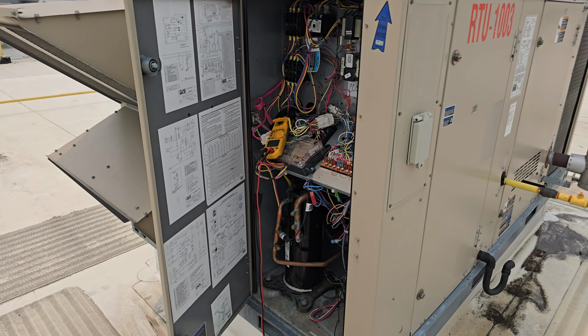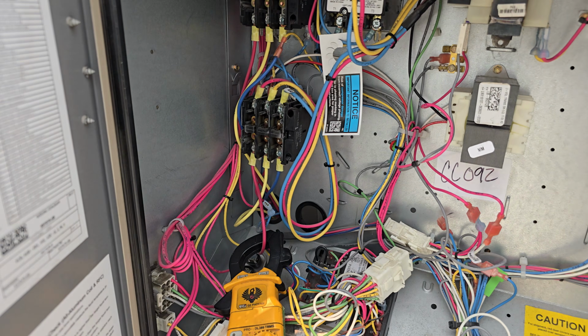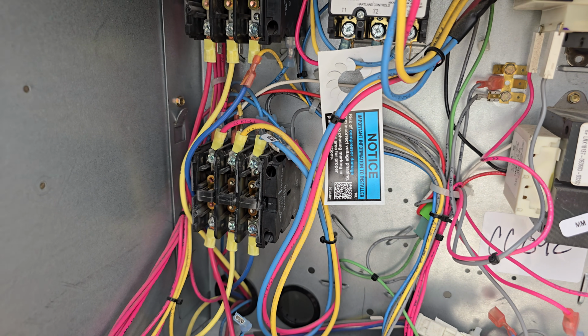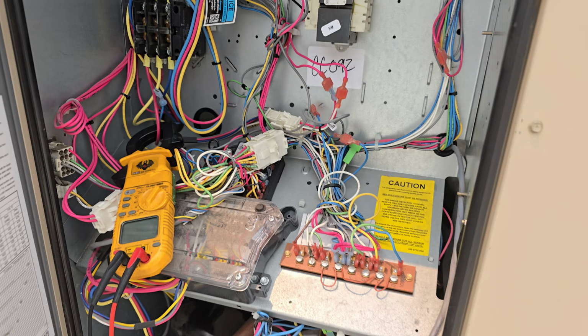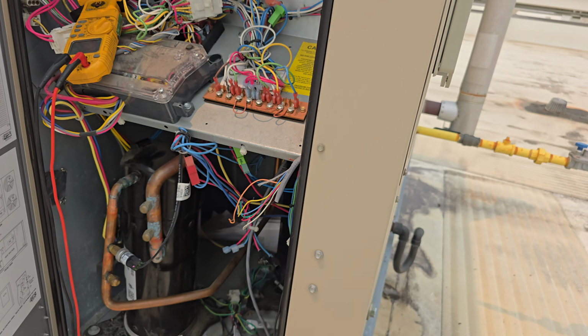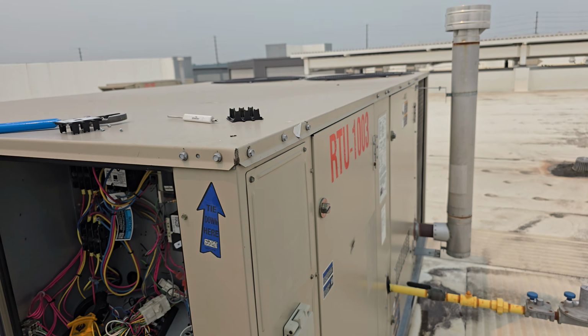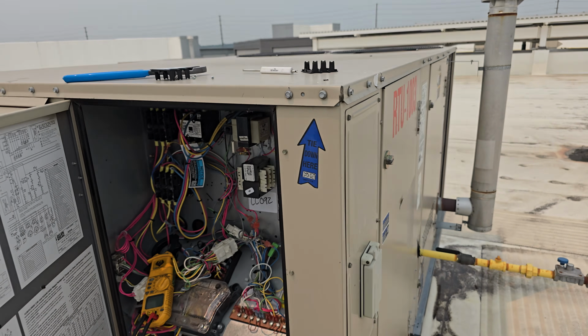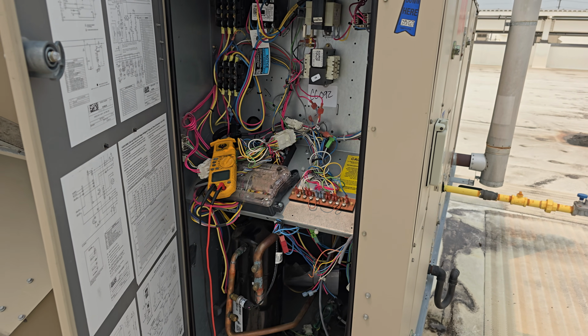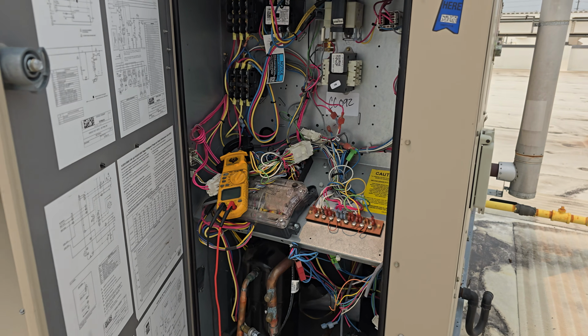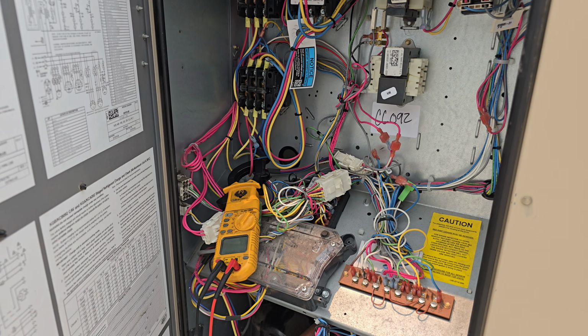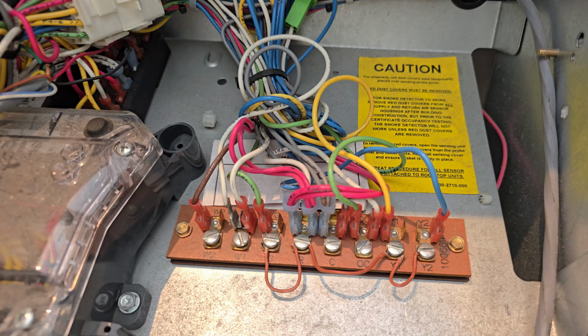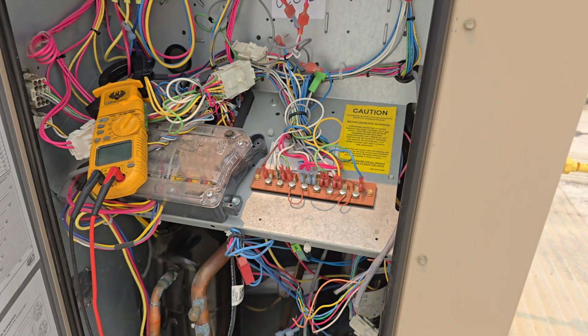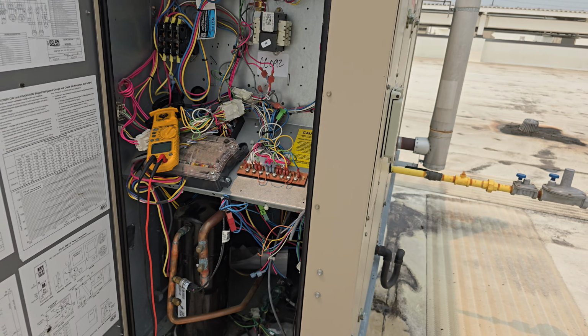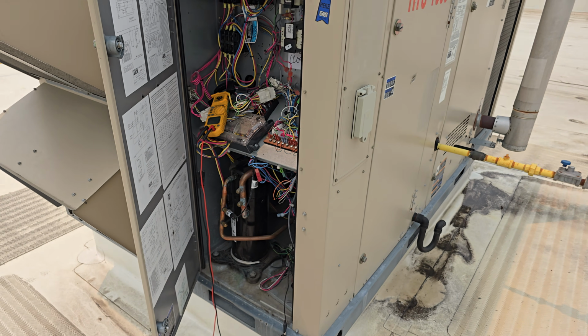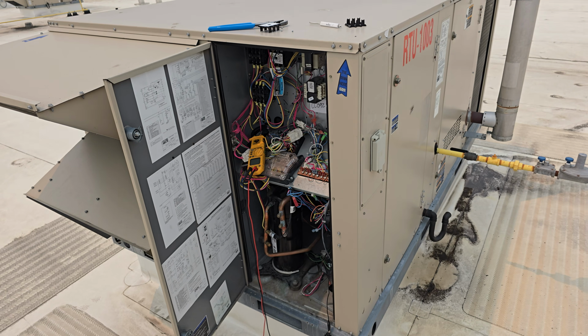Okay, so I disconnected all the low voltage wiring to this contactor, and the compressor has not come on, and my condenser fan has not kicked in, but my blower is running. So I'm going to wait and see if it's going to kick in, even though I energized my Y1 and Y2 asking the compressor to kick in. I'm going to observe and see what's going on here. Again, stay tuned and I will keep you updated.